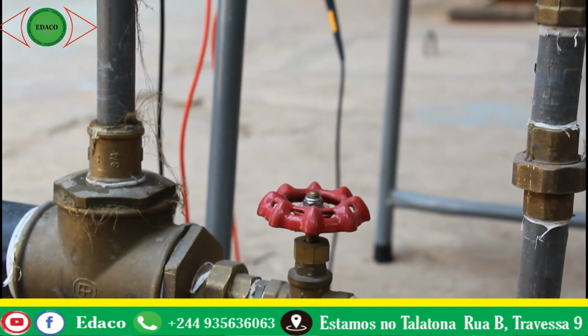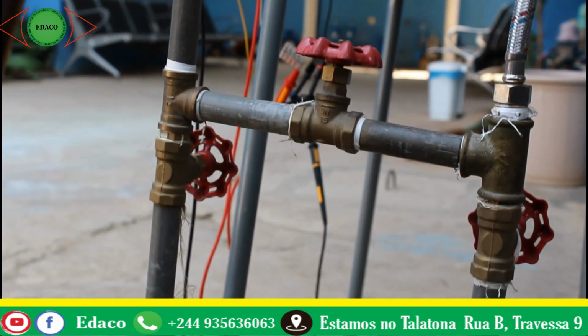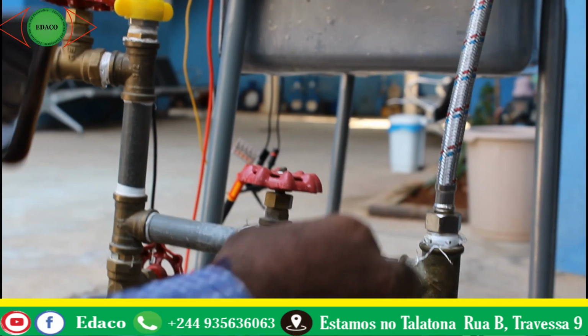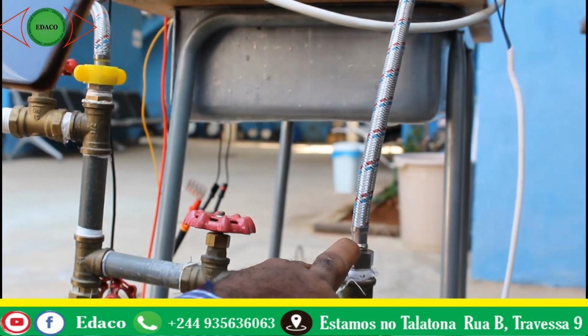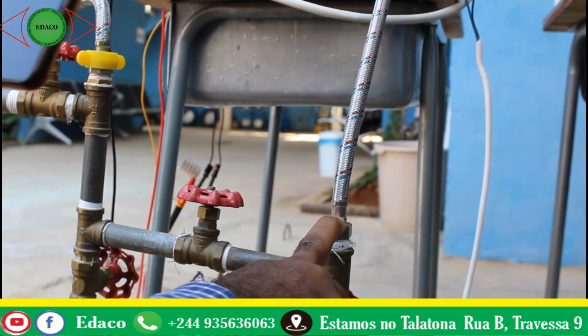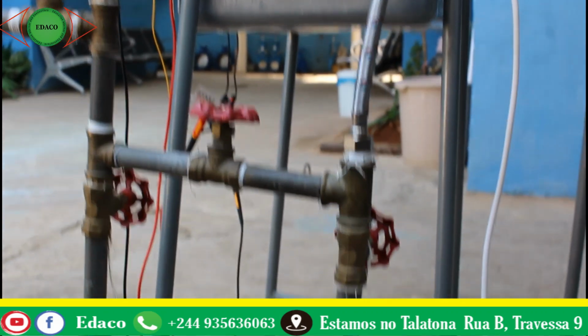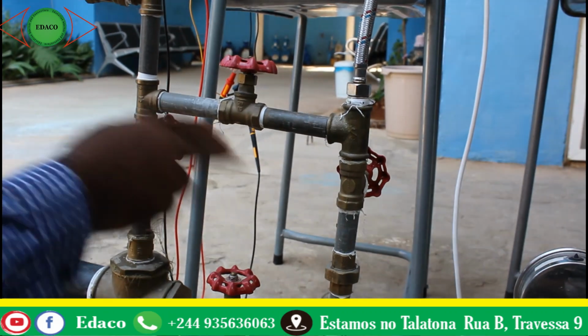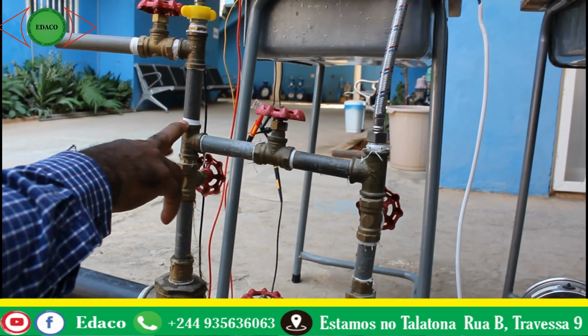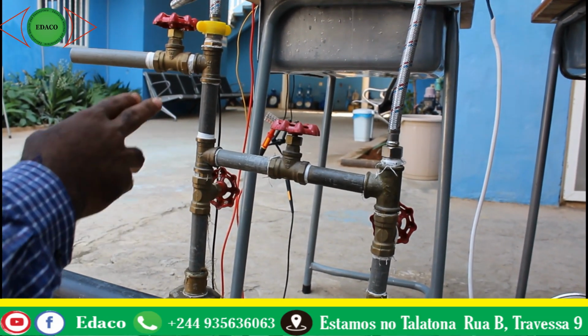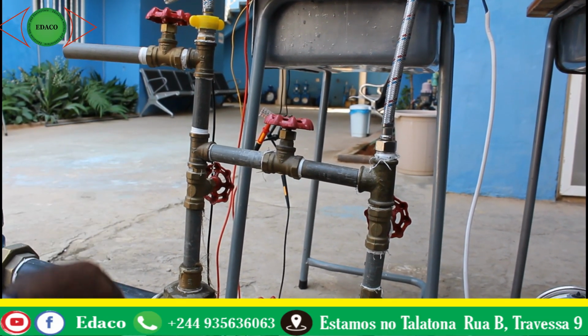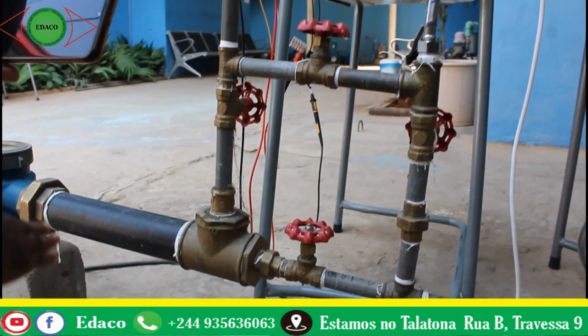And here we have our manifold. We connected the low side of our transmitter to the small diameter, and the high side to the bigger diameter side, because this is our inlet.